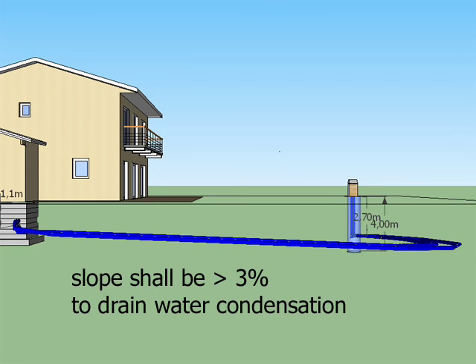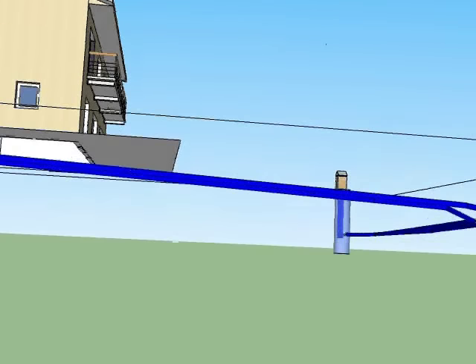The slope has been chosen above 3% due to the water condensation which has an opposite flow from the air in our case.